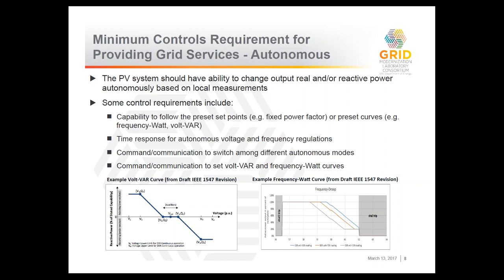In PV's case, for providing this autonomous service, you basically have to have the capability to change output real and reactive power autonomously based on some local measurements, such as voltage and frequency. So you have to follow preset set points or a preset curve. You have to have a specific time response, because it cannot be too slow for the time scale of a particular grid service. You have to have the command and communication to switch between different autonomous modes, and then you may have command communication to set different curves.